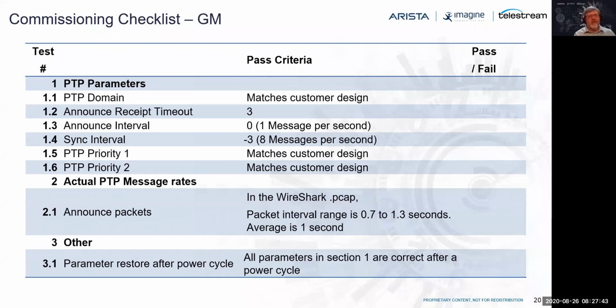This is just a very small fraction of the checklist, but just to give an example, say in the grandmaster, you're going to want to make sure, are the priority values set right? The priority 1, the priority 2s. You want to look at the announce messages leaving the device. What's the acceptable range? Even though you set it to 1 message per second, the standard has a certain distribution around that, so you want to make sure it's within this distribution. As I said, this is just a very small fraction of the parameters to check, but it gives you a sample of how you'd structure your checklist into various sections based on the parameters, how to measure them, and other parameters.